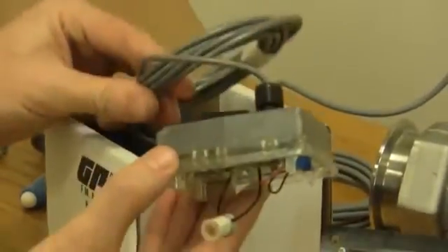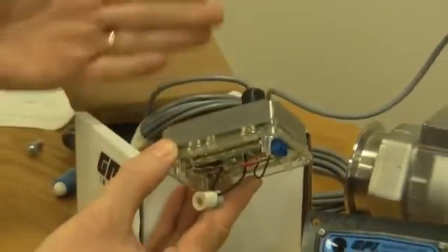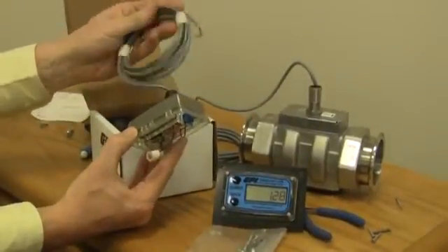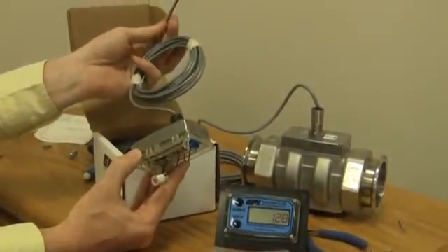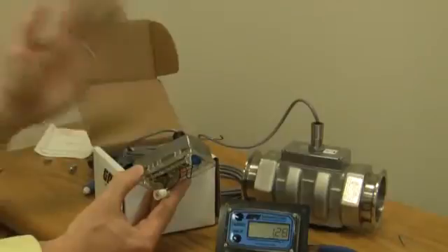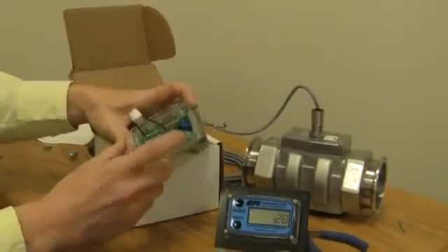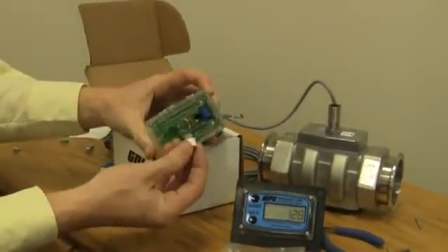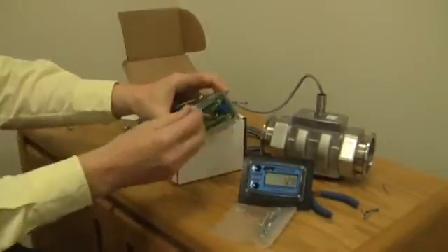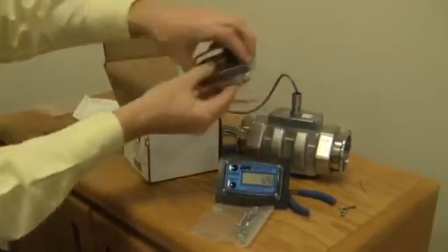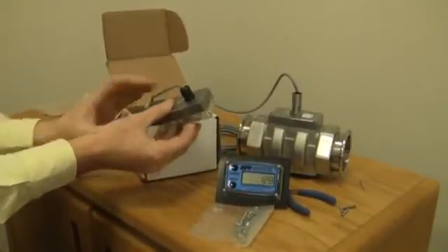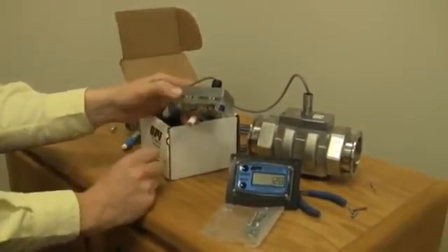So here, this is potted. This cable is part of this magnetic pickup, while this one is not. It goes through it, connects up to terminals. One of the other reasons I like this one better is because if you were going to go over that 10 foot length and you were going to say 20 or 30, you could extend this cable like I was talking about, but you can also replace it with one solid piece because again these are just little screw terminals. It's the same type of magnetic pickup as you had before so it can go right on top of there. Everything else is exactly the same.